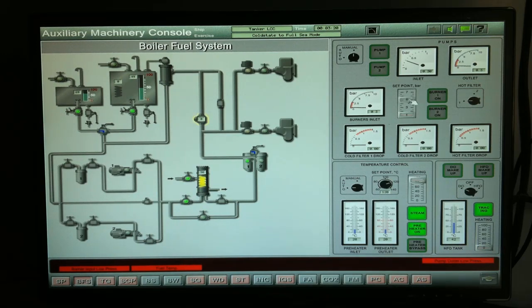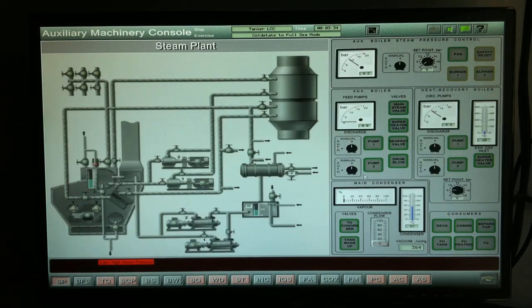Pressure set point 5 bars. Stop valve of the burner 1 and 2 open. Start the pump. Put it on auto. Okay, leave it running. Check on the boiler. Okay, so we need to pre-purge the boiler. So manually we turn on the fan to pre-purge the boiler.